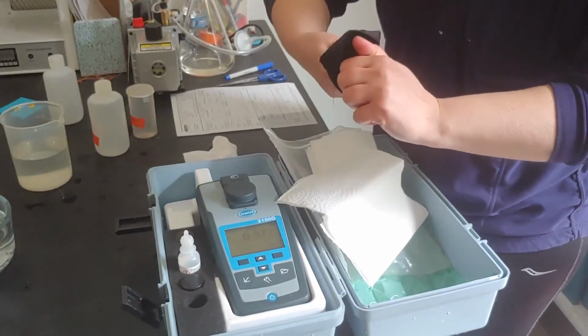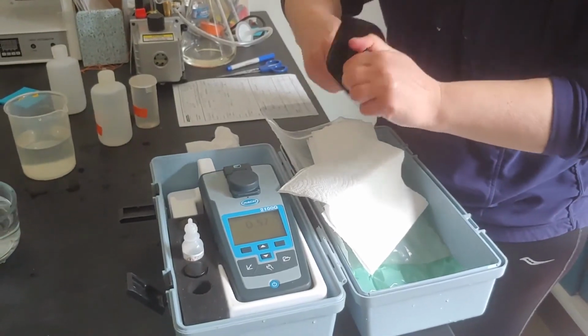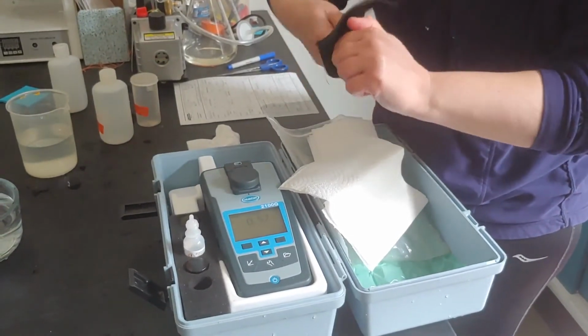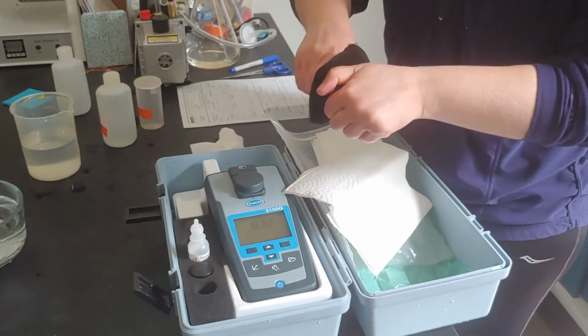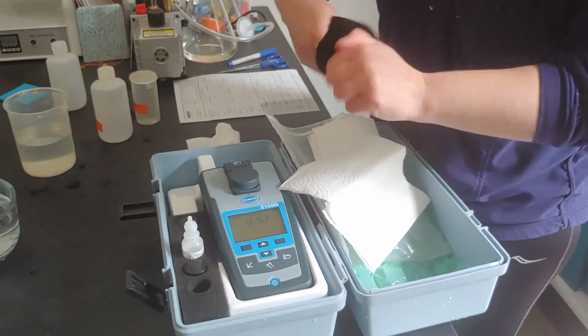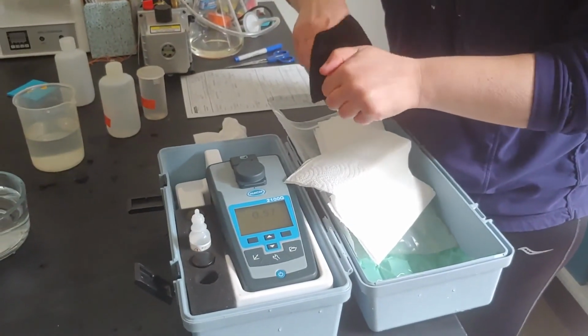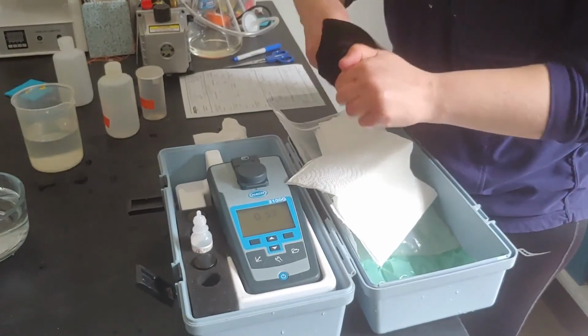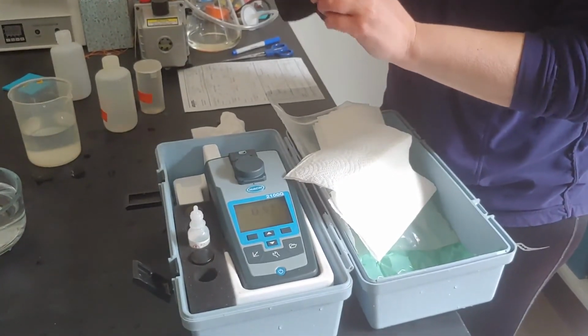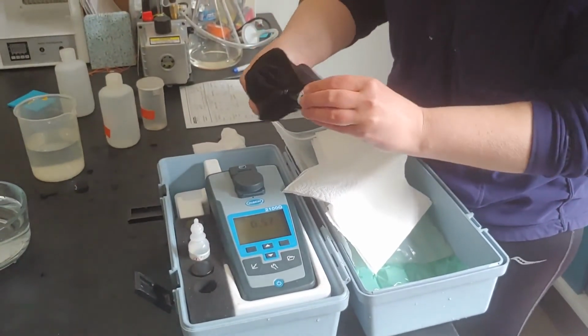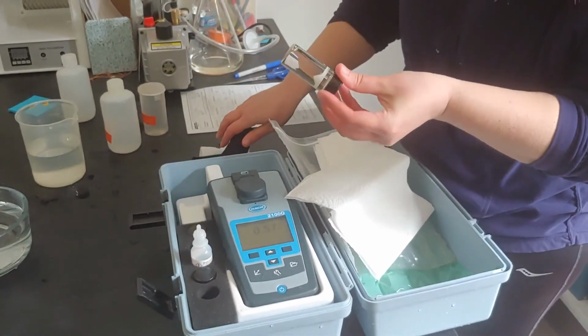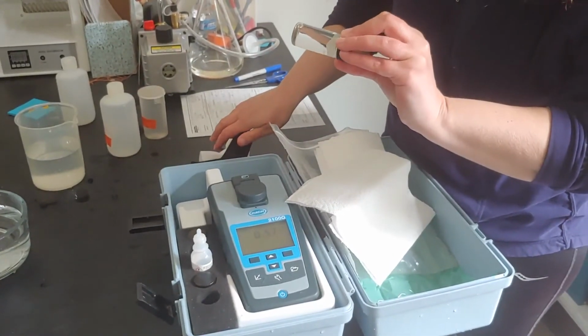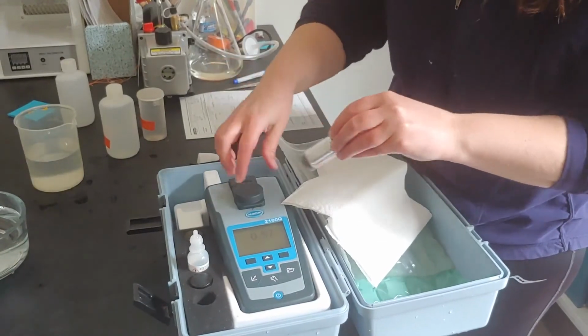This is doing a few things. We're getting rid of any fingerprints that may be on the glass, and the oil is filling in any scratches that may be on the glass from use. We want to try to get the best sample that we can that is of just the water and not have glass interference. Once I have spread my oil around, I want to just check quickly and make sure that I don't notice any major damages in the glass that may interfere with my sample.